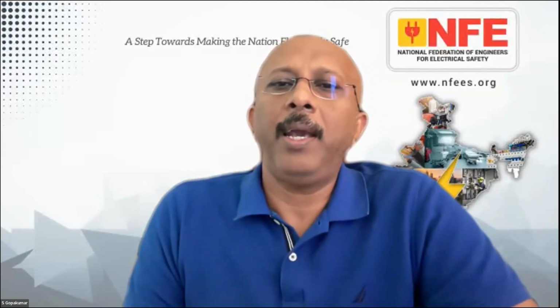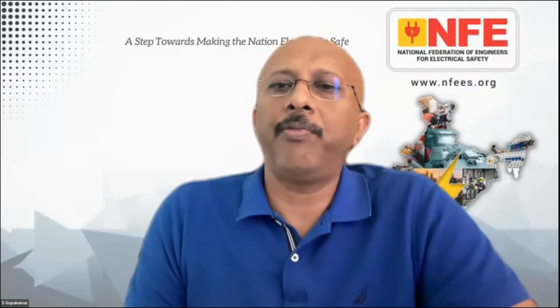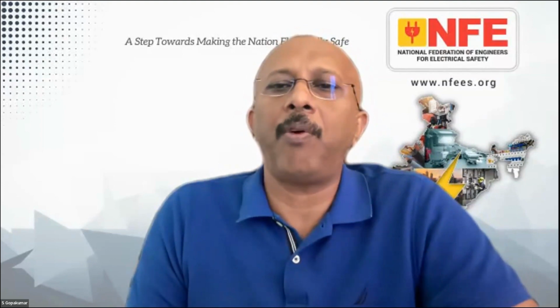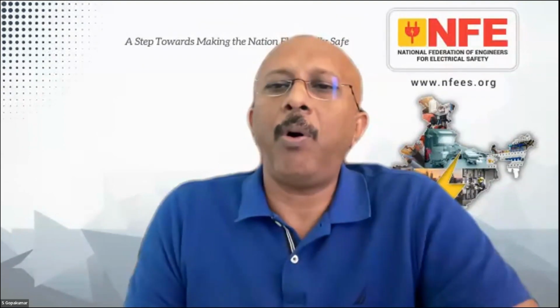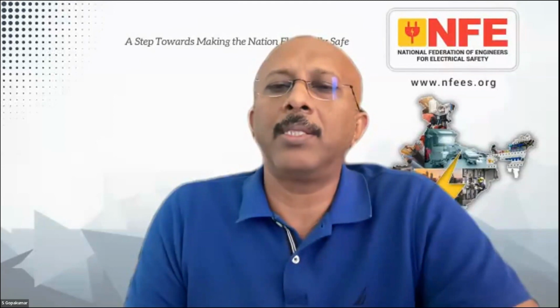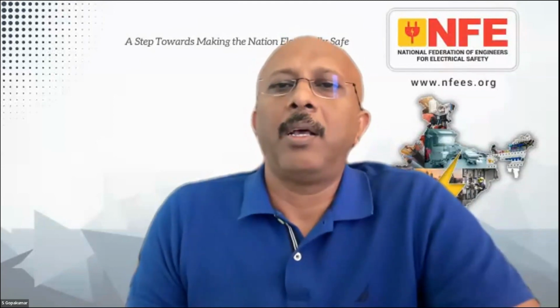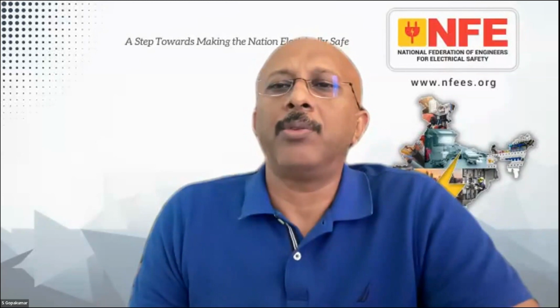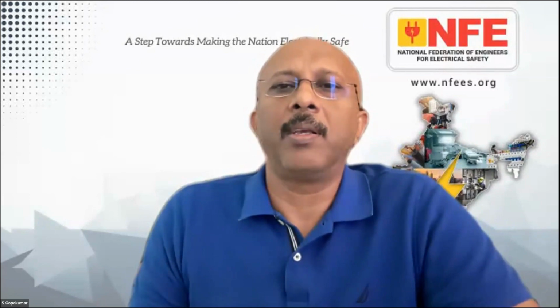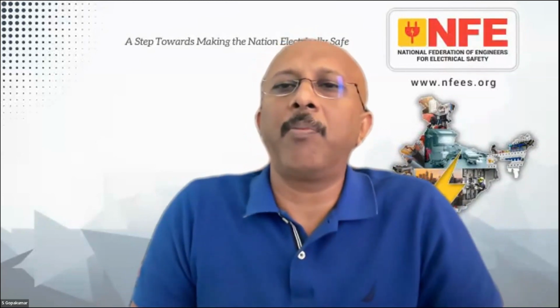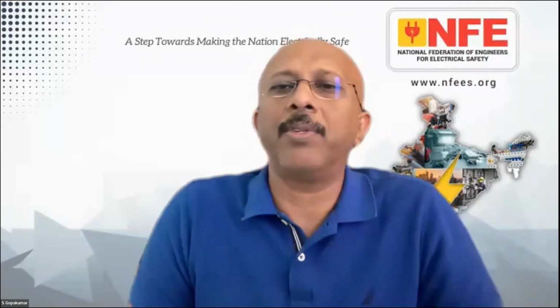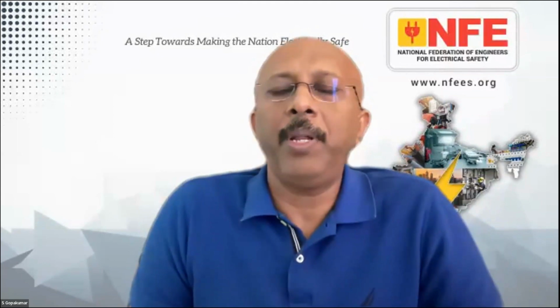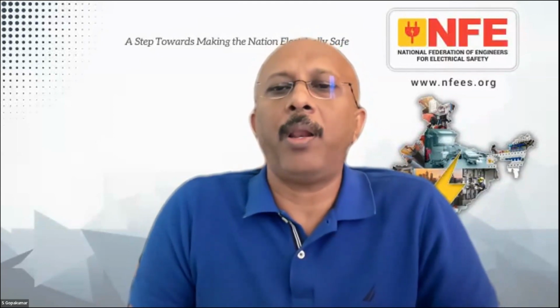To the next question, Mr. Vishal: if we have a series of distribution feeder pillars in between the supply transformer and the service installation, then how do we measure fault loop impedance? Will it involve all feeder pillars or only the feeder pillar closest to the service installation? Actually, the question is not very clear to me. The impedance is measured at the point where you are making the measurement.